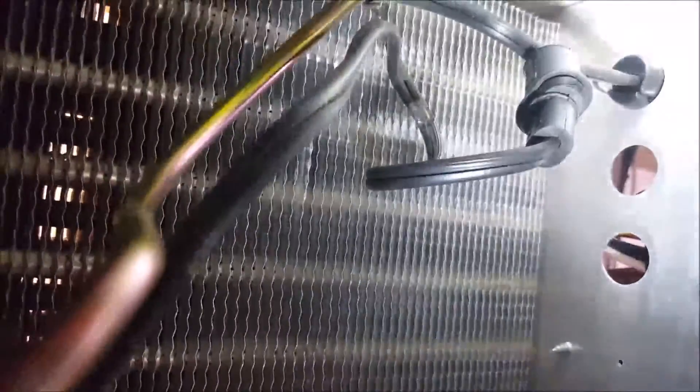A lot of these fan motors have a little quick connect, as you can see right there. They just unplug and then they plug back in. Those do come apart, so if you got a fan motor not working, check that first. Now, if you can see from here, also see that wire back here, it's got a nick in the wire.